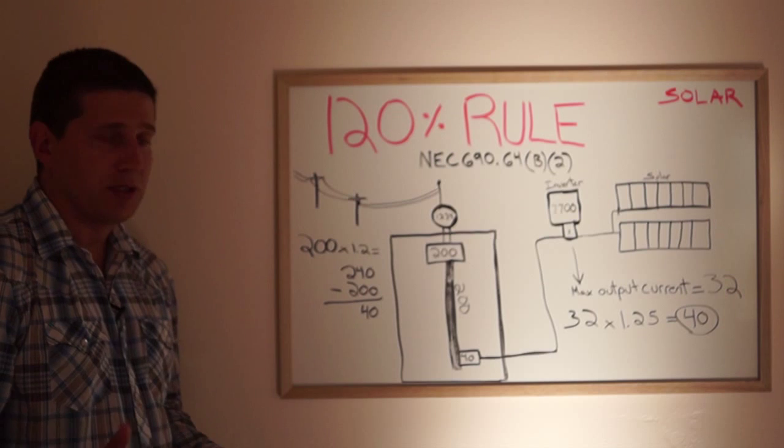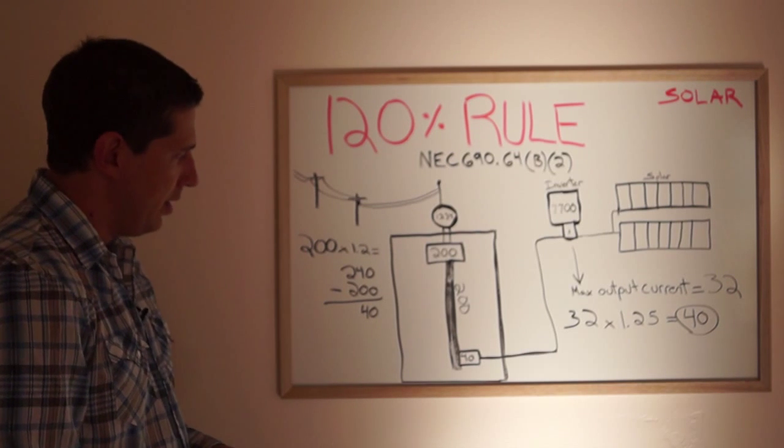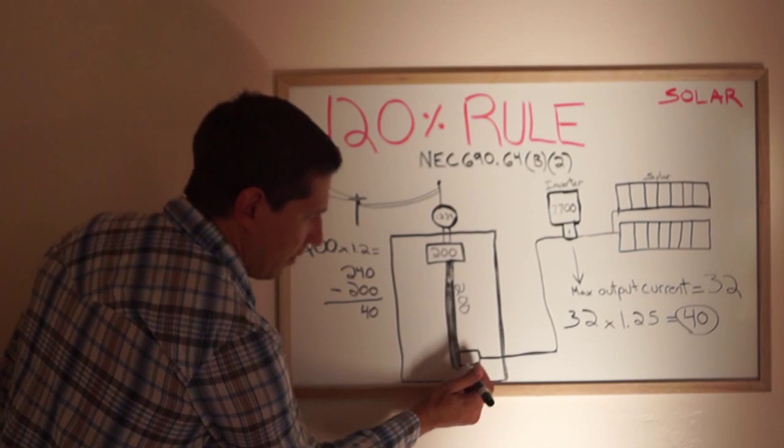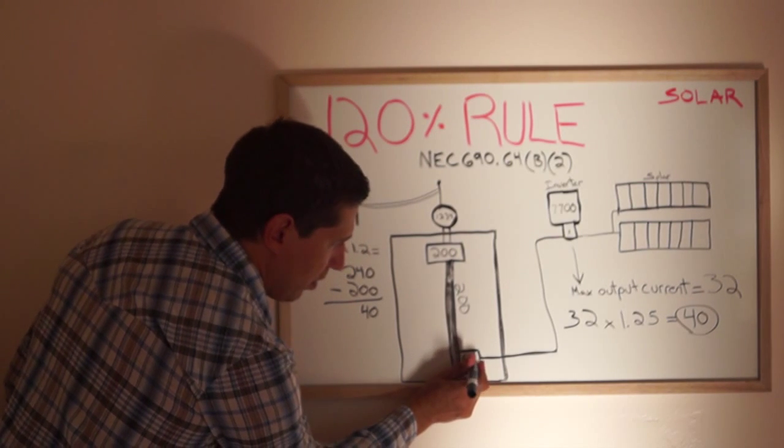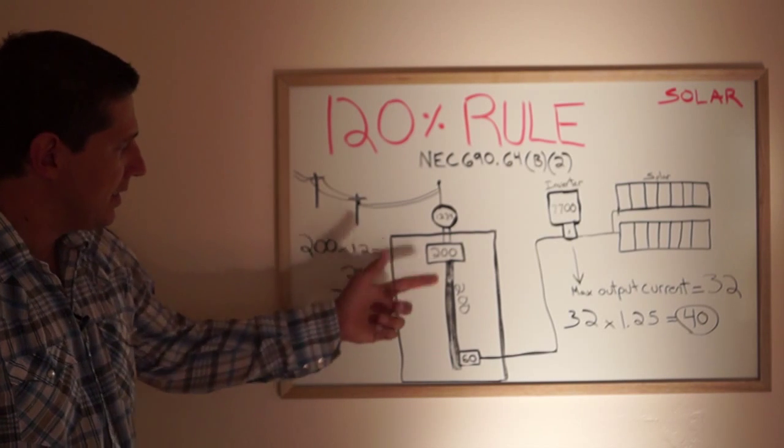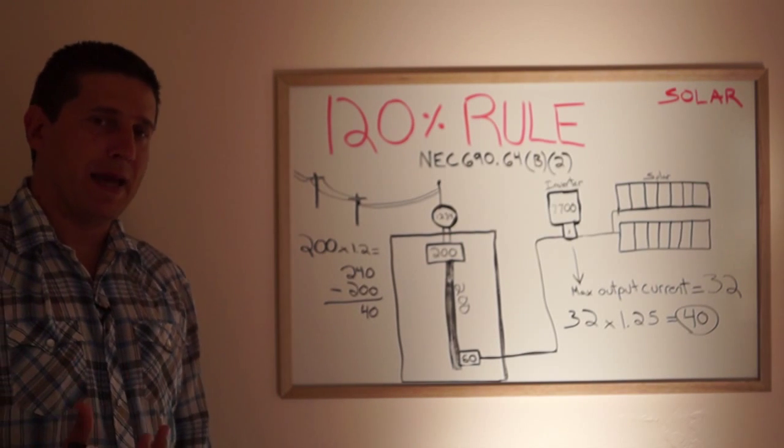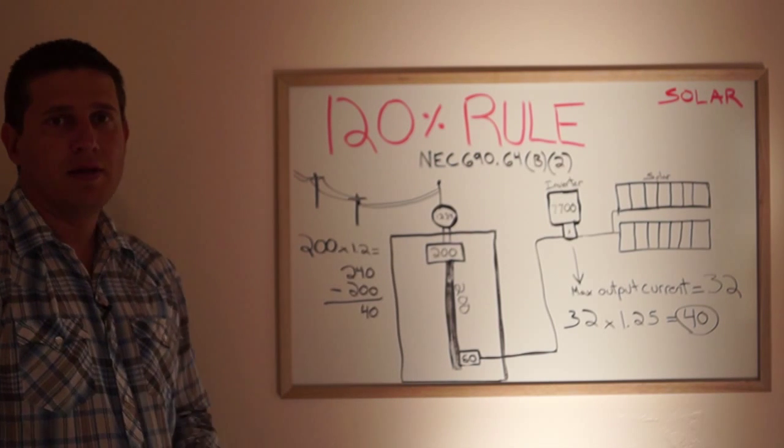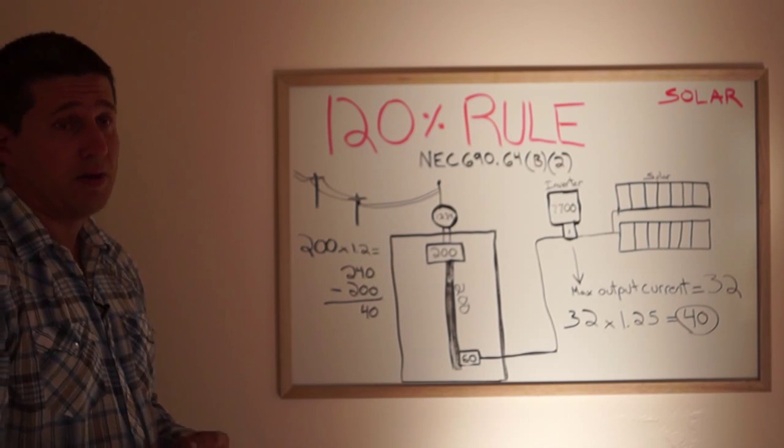Now let's say you wanted to add a larger system. Let's say you wanted to add 60 amps of solar to this main panel. We're 20 amps over capacity, right? We're 260. 260 amps could potentially hit this main bus bar causing a fire which is why the code exists.